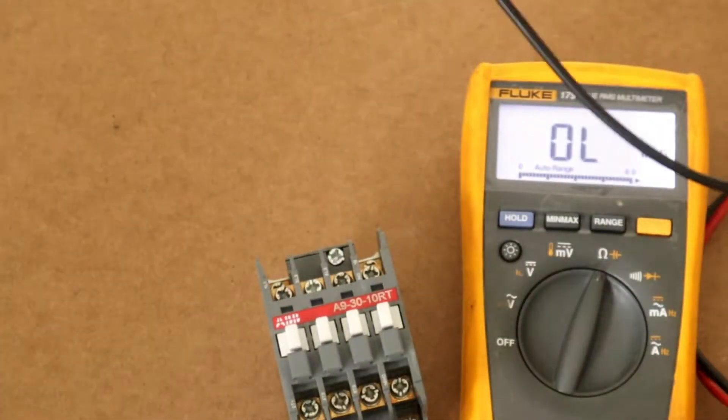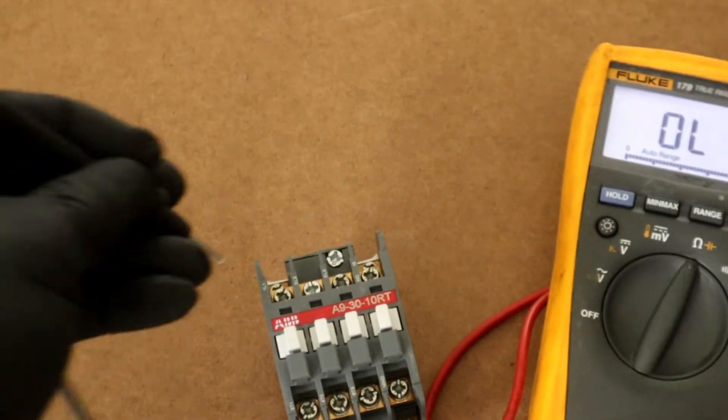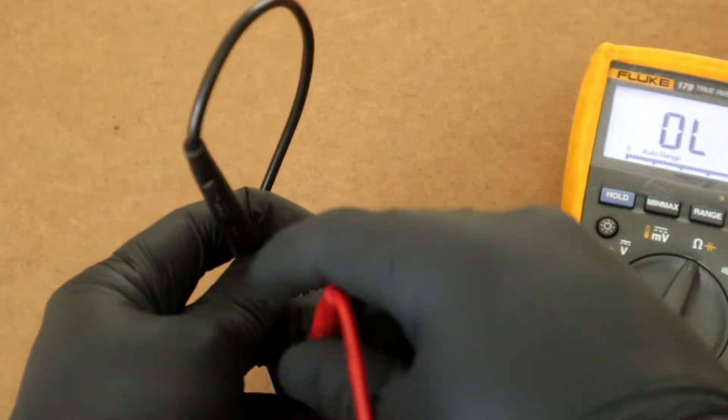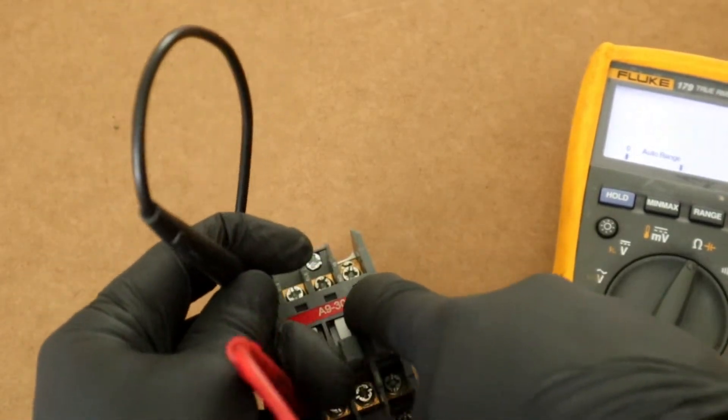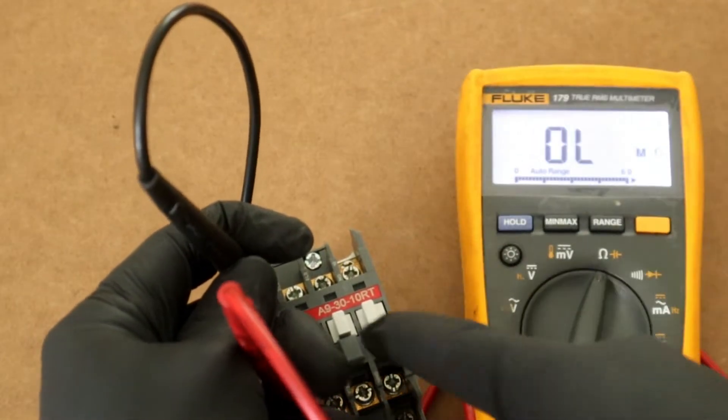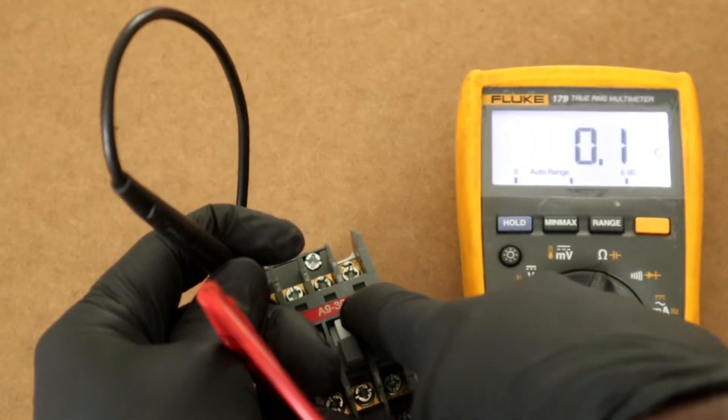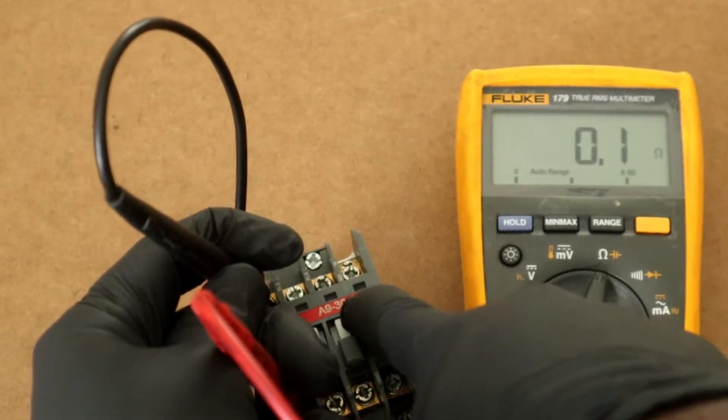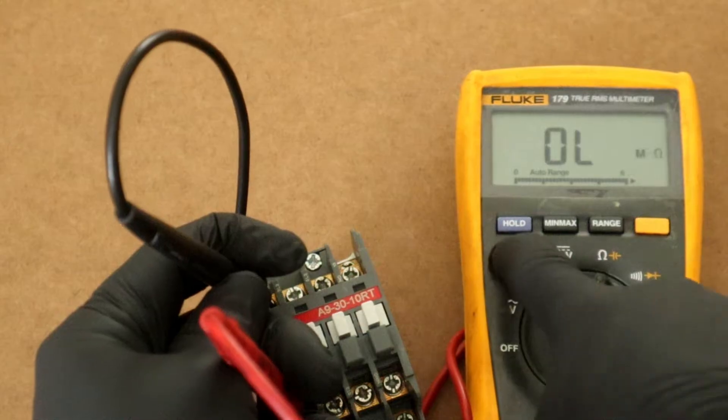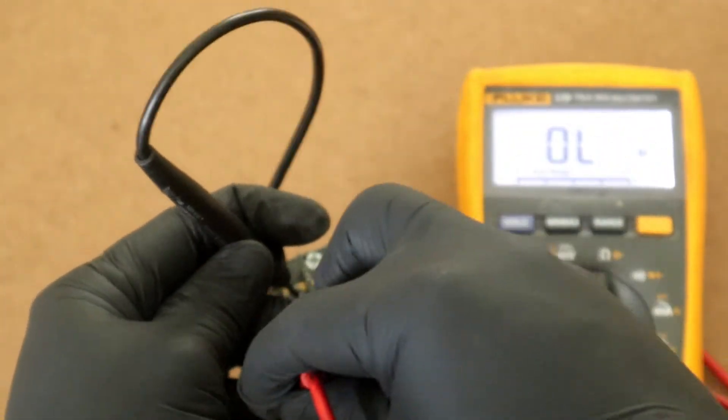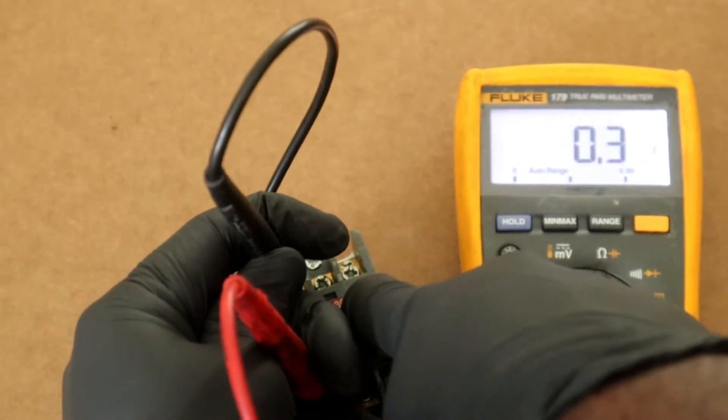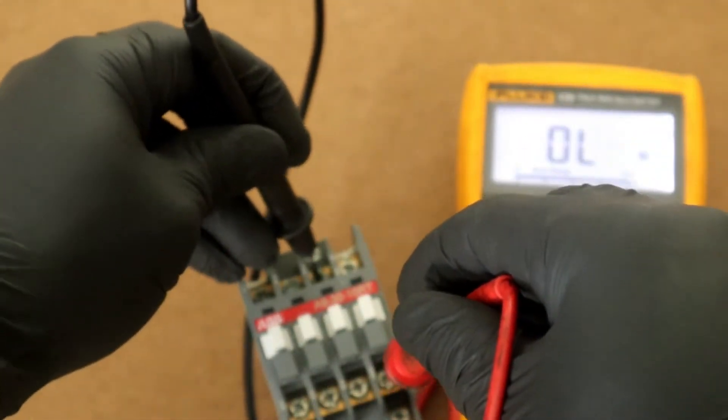We're going across L1, T1. Push it in, we have 0.1 ohm. So we have continuity across L1 to T1. L2 to T2, manually depress, 0.2 ohms. We are good so far for L2 to T2.